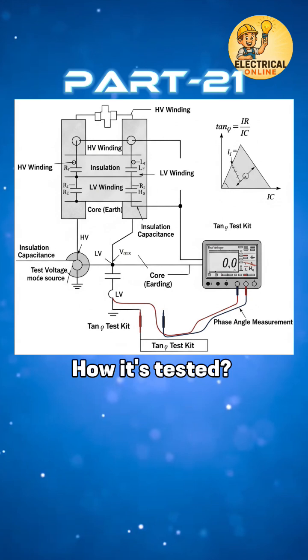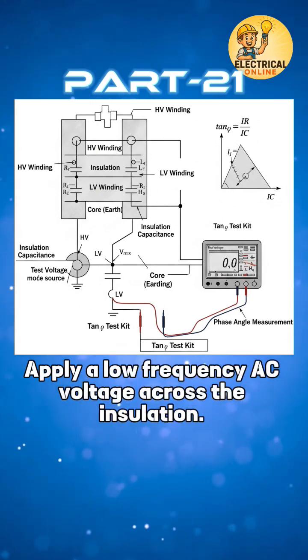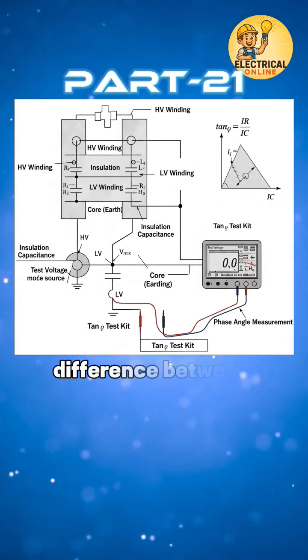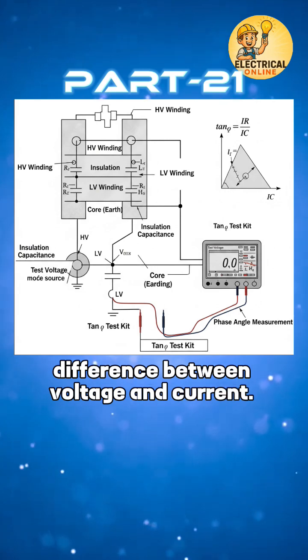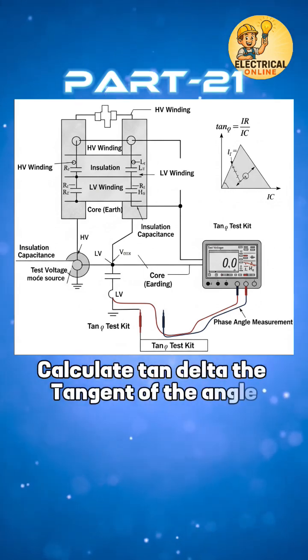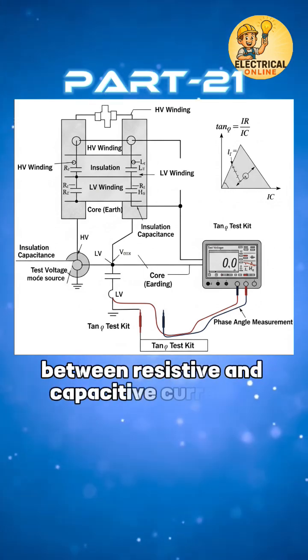How it's tested. Apply a low frequency AC voltage across the insulation, measure the phase difference between voltage and current. Calculate tan delta, the tangent of the angle between resistive and capacitive currents.